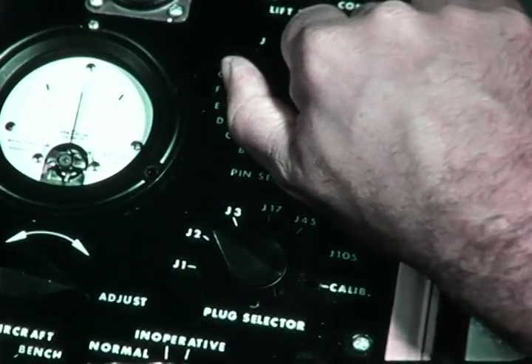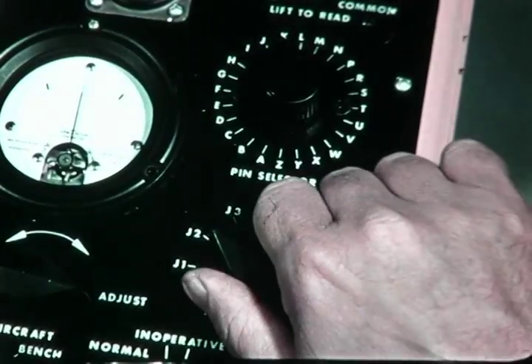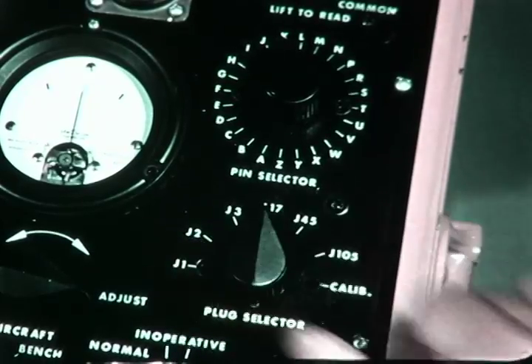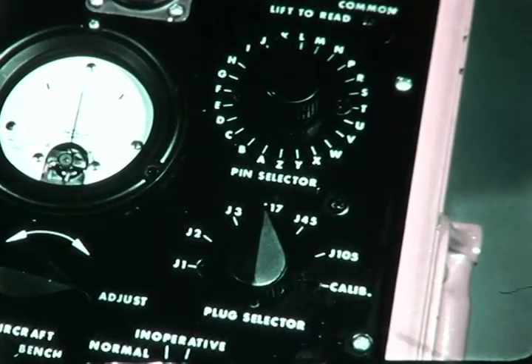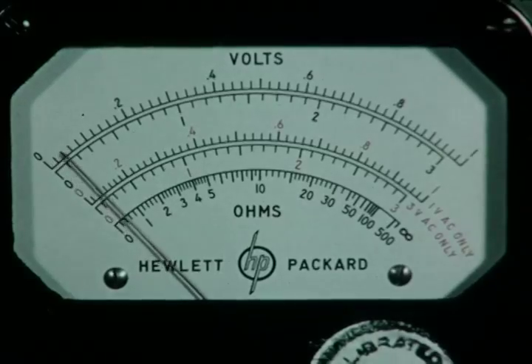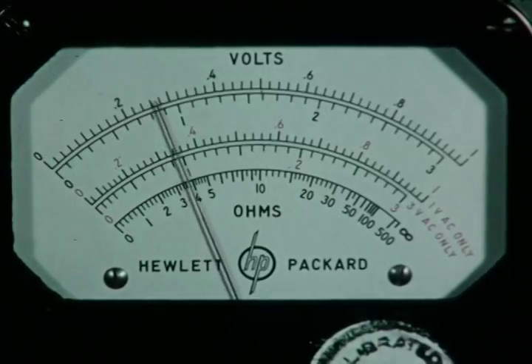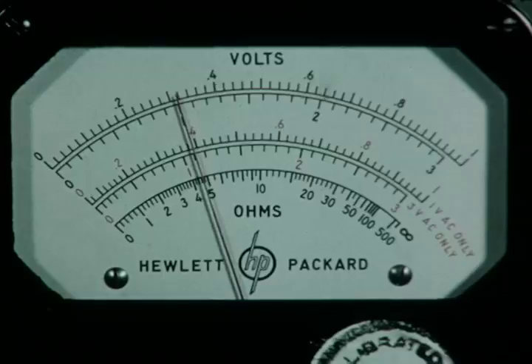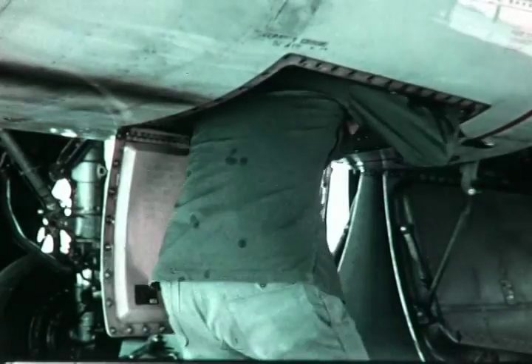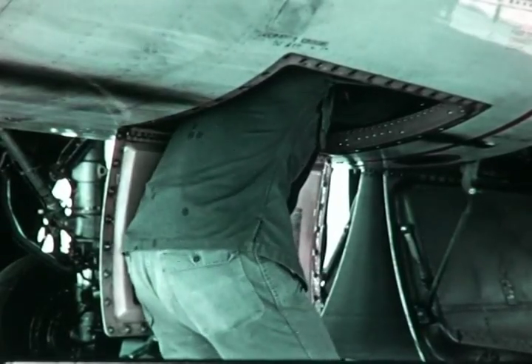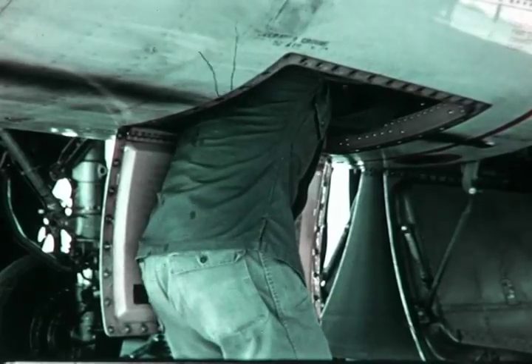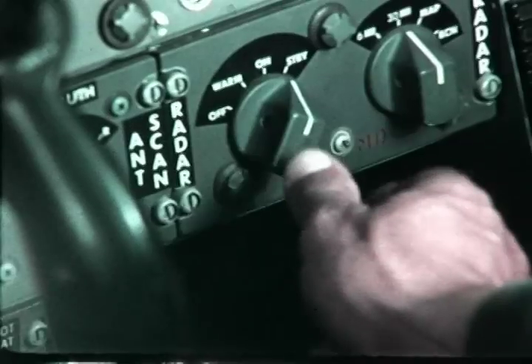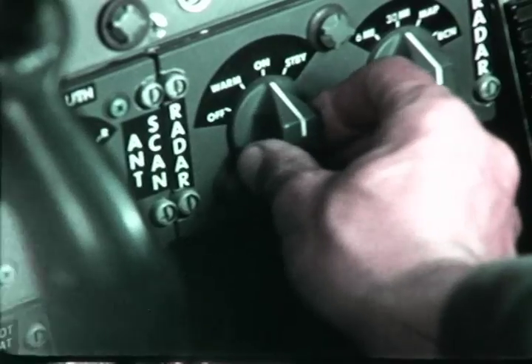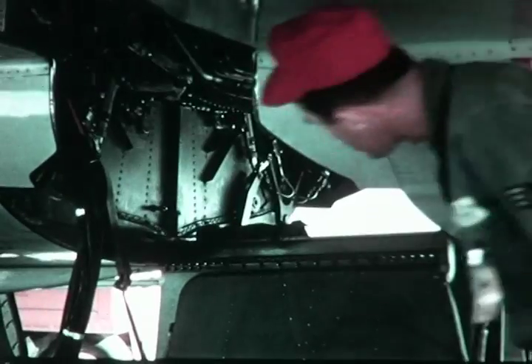Next, we test the AFCS plus and minus 105 volts using the J17 plug and pin J. The limits here are between 100 to 110 volts. Next, we adjust our aileron position pot to null and minimize the yaw damper engage shift. Put the radar switch on warm. The elevon trim and rudder trim circuit breakers are opened.